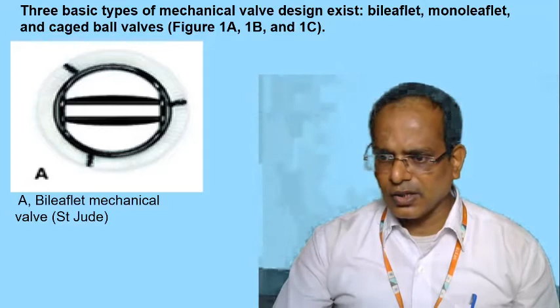The bileaflet valves are made up of two semilunar discs attached to the rigid valve ring by small hinges, that means movable joints. The opening angle of the leaflet relative to the annulus plane ranges from 70 degrees to 90 degrees, and the open valve consists of three orifices. The first is a small central slit-like orifice, and the other two are between the open leaflets and the ring, two larger semicircular orifices laterally connected.